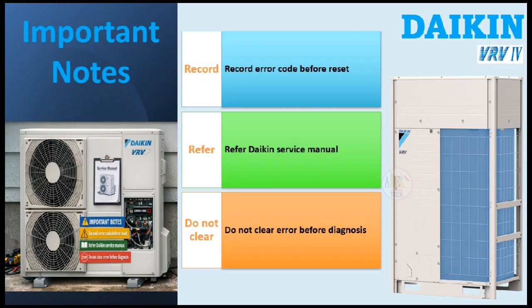Technical notes and best practices. It is strongly recommended to record both the main code and subcode before resetting the system. Always cross-reference the displayed codes with the Daikin VRV service manual to ensure correct diagnosis. Avoid clearing error history before completing root cause analysis, as this may result in repeated failures or misdiagnosis.